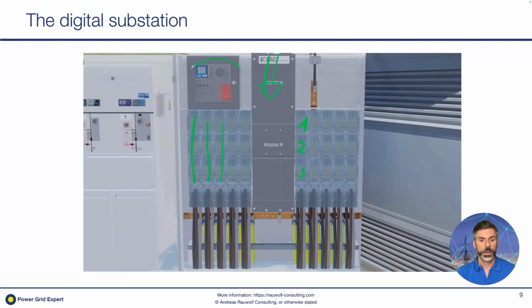And what we have here is a first element of a more digital substation. This is, let's say, a built-in multimeter that monitors voltage and currents, plural, coming from the transformer. So we already get information on what's going on here, what is the total supply of all the low voltage feeders that are connected to that transformer. That's already great. In old times, this has been done with these analog meters. And with the digital version, of course, we can connect them to a SCADA system. We can check the maximum and the minimum values and more stuff.